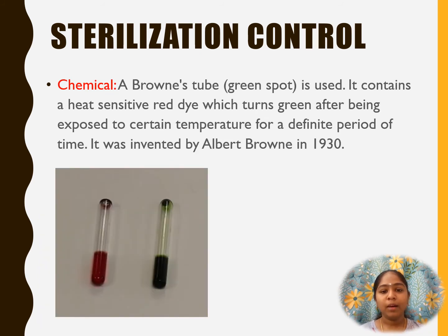Chemical method. A Browne's tube is used. It contains a heat-sensitive red dye which turns green after being exposed to a certain temperature at a definitive time. A green color is produced after 60 minutes at 160 degrees Celsius or 115 minutes at 150 degrees Celsius, proving or suggesting a complete sterilization.